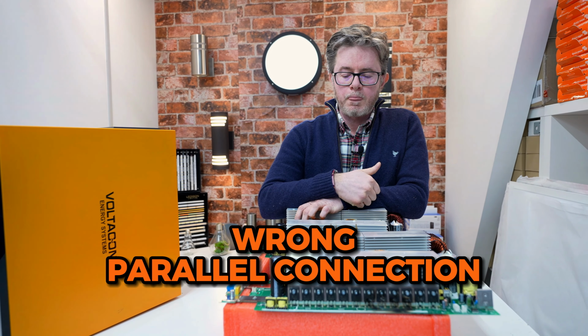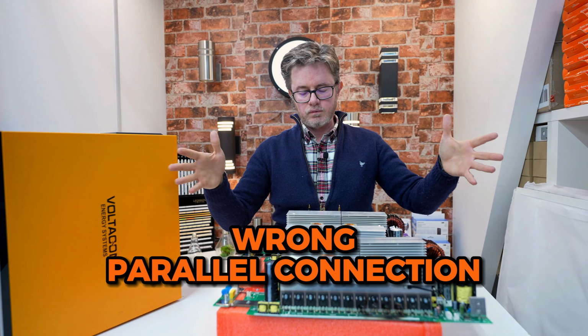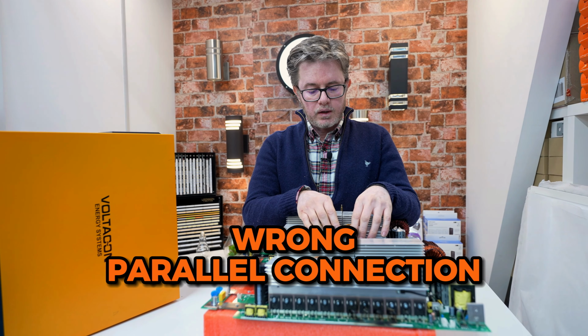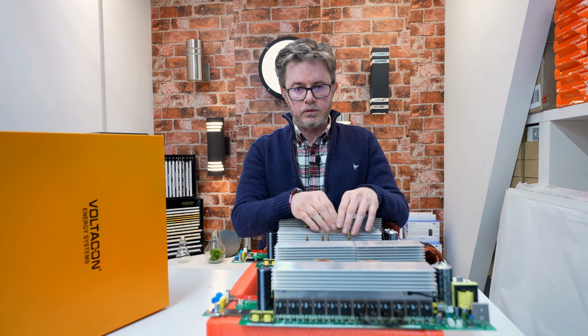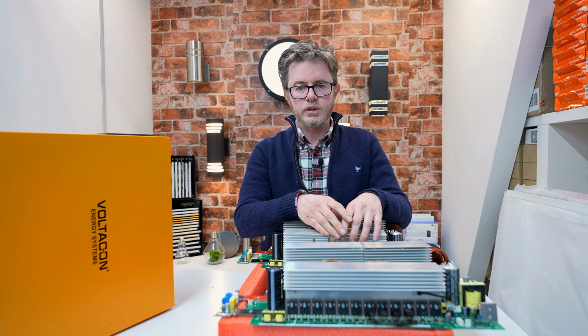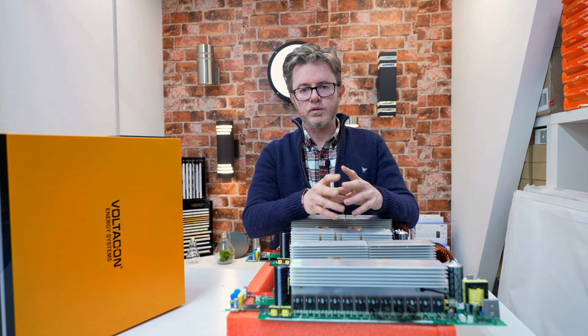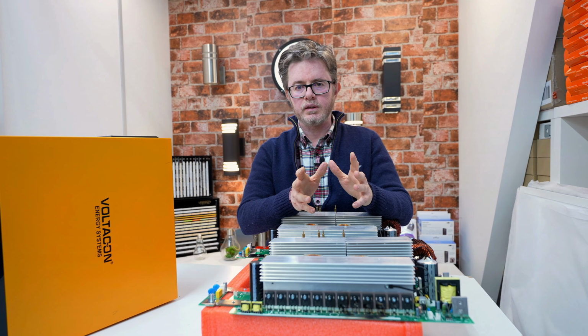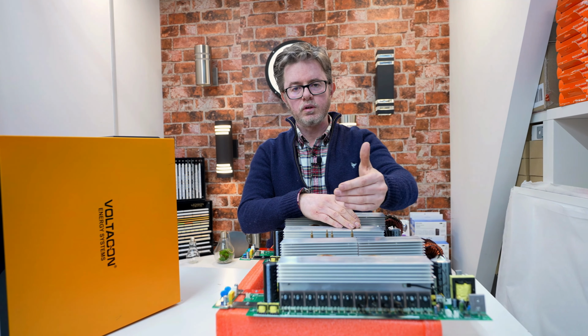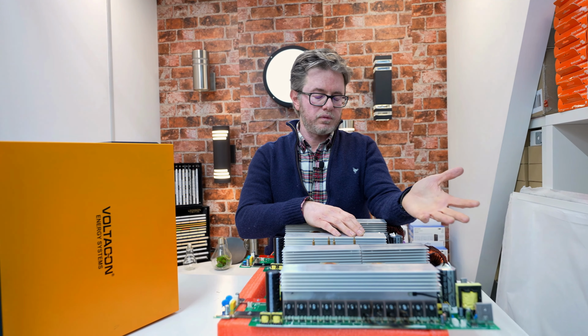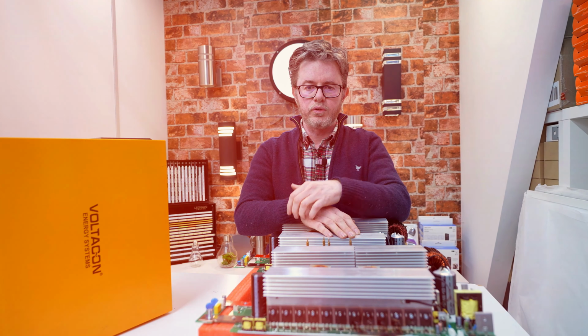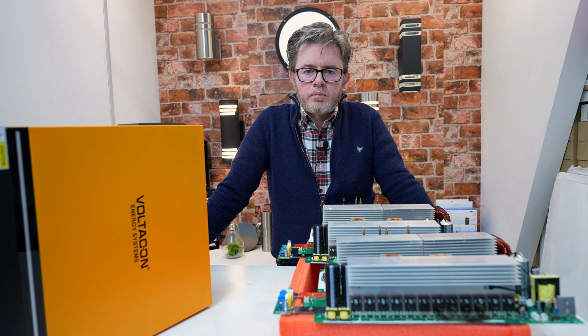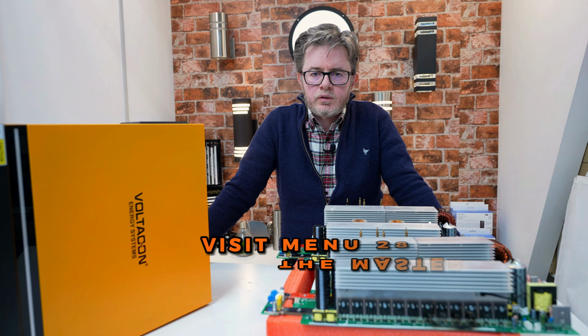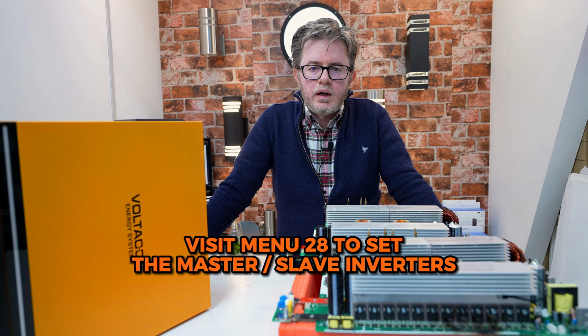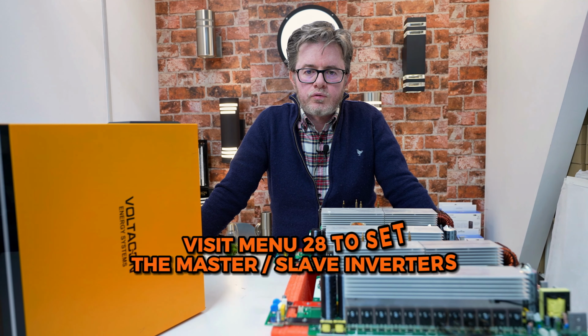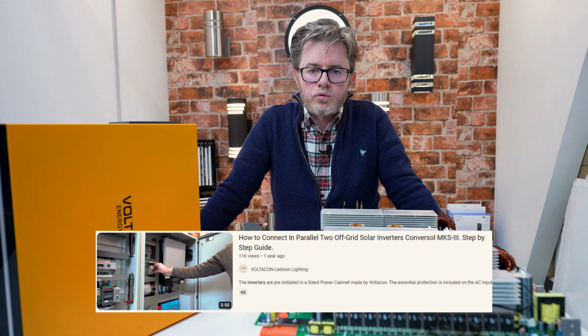Reason number two: many customers get 2, 3, up to 6 inverters in parallel. If they are not connected properly together, if the parallel connection kit is not connected to the right terminals, this is going to create a huge circulating current. And again, the IGBTs will blow up. It can be the IGBTs, the capacitors, or both. Just a quick note to visit menu 28 of the inverters, the master and slave. And if you want, please watch our video on how to parallel solar off-grid inverters.